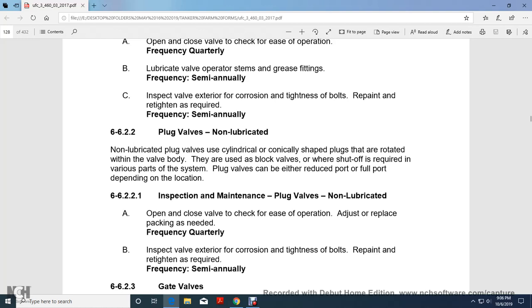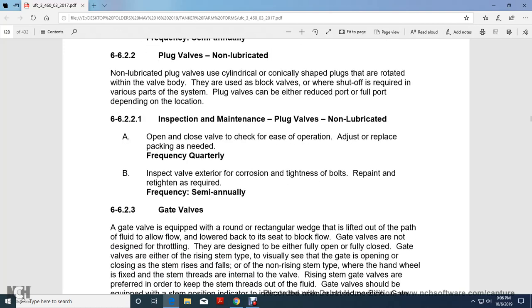Plug valves can either be reduced port or full port depending on the location. Inspection and maintenance of plug valves, non-lubricated: open and close the valve to check for ease of operation, adjust or replace as needed, frequency quarterly. Inspect the valve exterior for corrosion and tightness of the bolts, repaint and retighten as required, semi-annually.